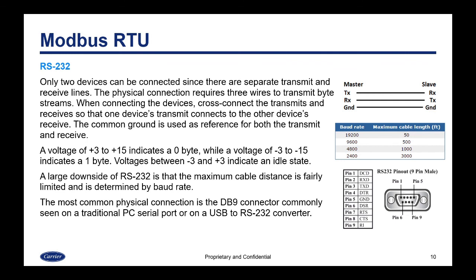Voltages between negative three and plus three indicate an idle state. A large downside of RS-232 is that the maximum cable distance is fairly limited and is determined by the baud rate. At 19,200 baud, for example, the maximum distance would be 50 feet. The most common physical connection is the DB9 connector, commonly seen on a traditional PC serial port or a USB to RS-232 converter, as shown at the right.